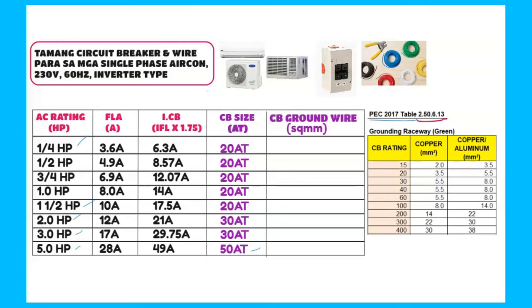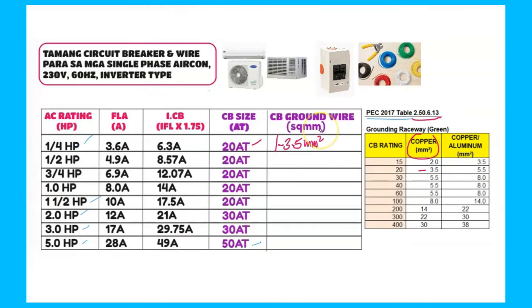So ang gamit natin is copper. From this column, ito yung CB rating. Then if you use aluminum, ito yung gamitin mong column. So from this 20 ampere circuit breaker, the grounding raceway is 3.5. So gamit tayo rito ng isang 3.5 mm square na grounding. And then the same with this until sa 1 1/2, that is 3.5 mm square.